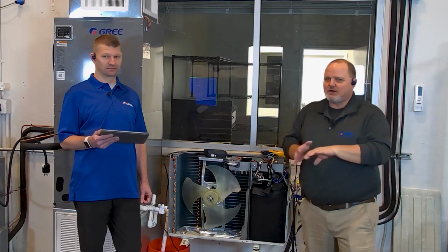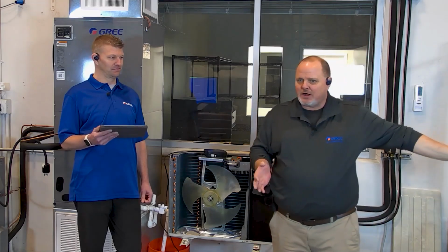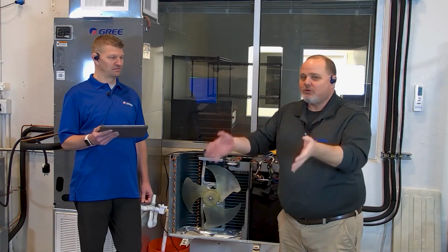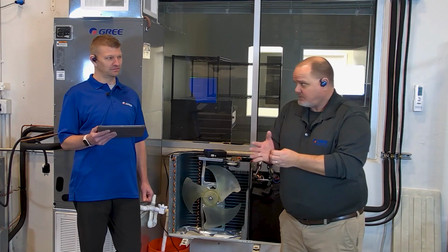So you know how much you added on this date, so that when you come back and you recover all that refrigerant out of there, you pull out that part that you just put in there, how much was left? You know, okay, this thing was definitely low. I got a leak somewhere here. I need to figure this out and get it fixed. So, again, the manufacturer's recommendation is going to be pull and weigh the charge, because that's the only way with a variable speed compressor we can assure the charge is correct.